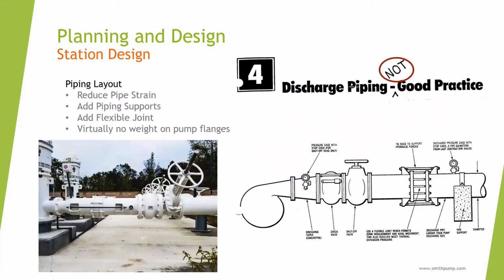Here's the second way to distort the discharge head: loading the flange with too much weight. Piping supports are crucial to a pump's life, especially vertical turbines. The perfect piping setup bears no weight on the pump flange and has a flexible coupling for perfect flange to flange alignment. The picture on the left shows no pipe support, so the pump has become the pipe support. The drawing on the right shows a pipe support, but it's too far away. These pumps are bearing most of the valve weight, and valves are heavy dudes.